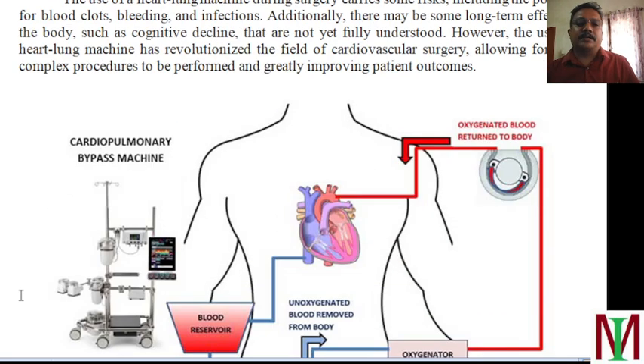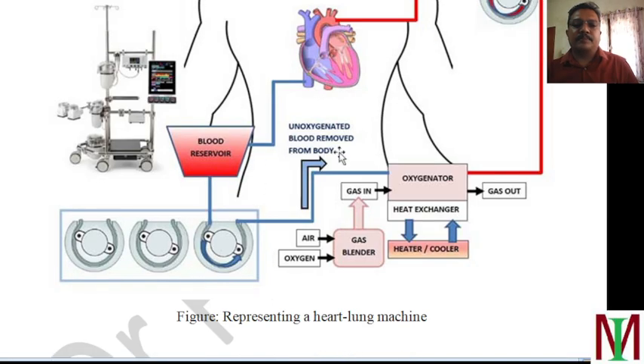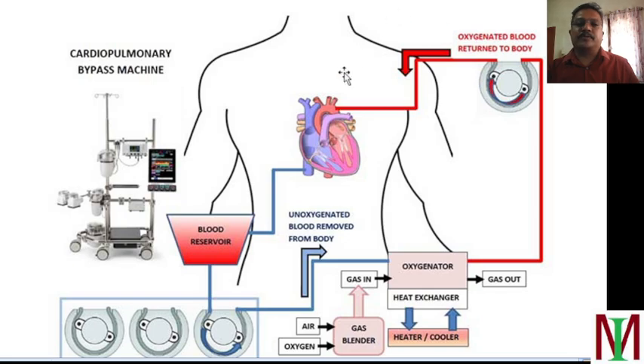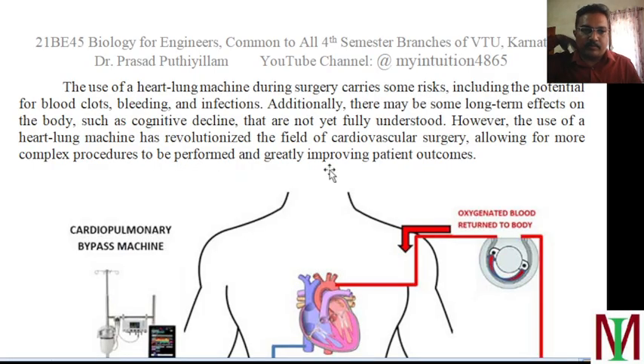Schematically, the heart-lung machine takes the blood stream, pumps it, oxygenates it, performs heat exchange — including cooling and heating — and then pumps it back to the body stream while the heart operation is being performed. Additionally, there may be some long-term effects on the body like cognitive decline, which is not yet fully understood by health experts. However, the use of the heart-lung machine has revolutionized the field of cardiovascular surgery, allowing for more complex procedures to be performed and greatly improving patient outcomes.